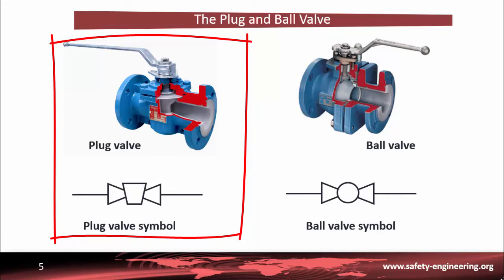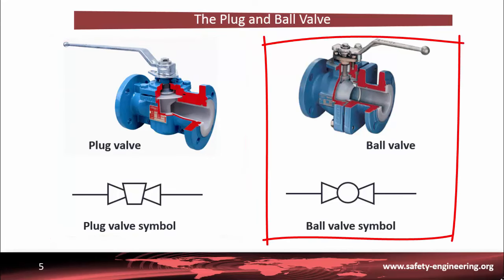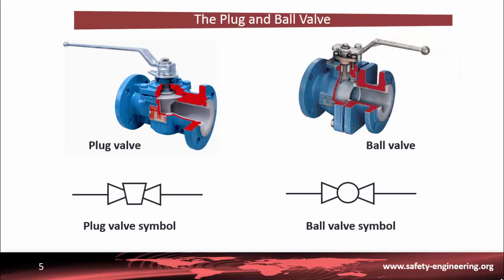Plug valves are similar to ball valves in operation. A ball valve is a quarter-turn rotational motion valve that uses a ball-shaped disk to stop or start flow. When the valve is opened, the ball rotates to a point where the hole through the ball is in line with the valve body inlet and outlet. When the valve is closed, the ball is rotated so that the hole is perpendicular to the flow openings, and the flow is stopped. The advantages are quick quarter-turn on-off operation, minimal resistance to flow, and smaller size than most other valves. The disadvantages are that these valves require a large force to actuate due to high friction, and have a reduced port due to the tapered plug.